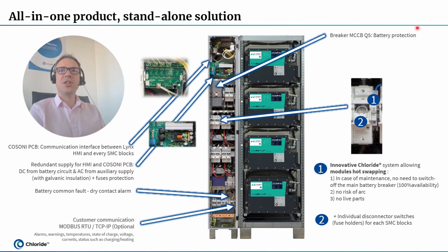We have integrated this general breaker MCCB for the battery protection. And we have integrated this innovative Chloride system allowing module hot swapping. So with this system based on this relay plus this fuse holder, in case of maintenance, there is no need to switch off the main battery breaker. I mean this one. No need, because with the combination of this switch plus this one, finally there is absolutely no risk of arc when you disconnect the power cable located there. So no risk of arc, no live part.